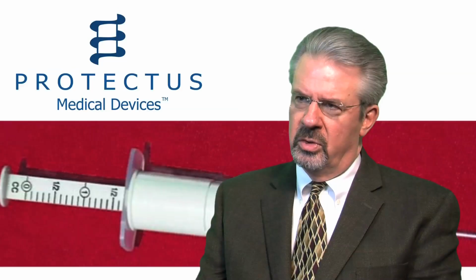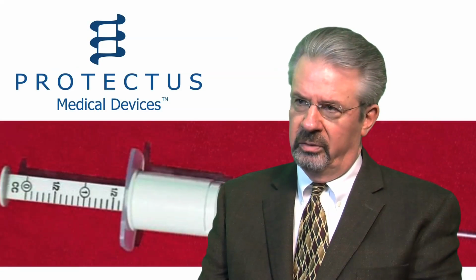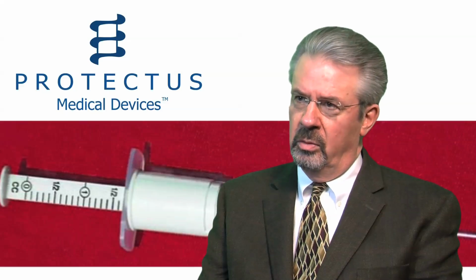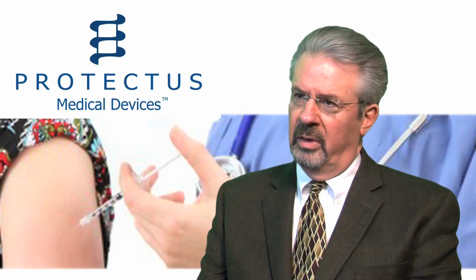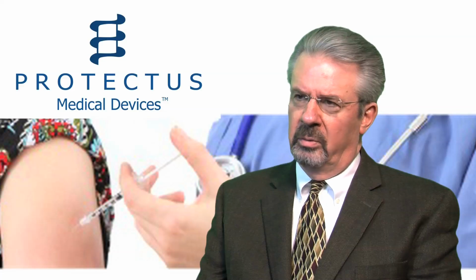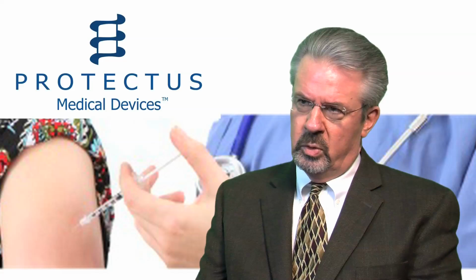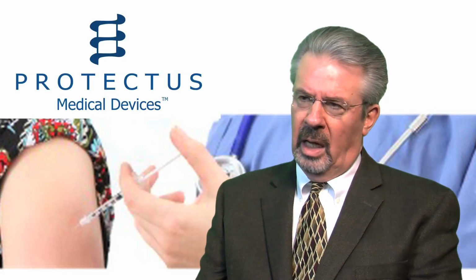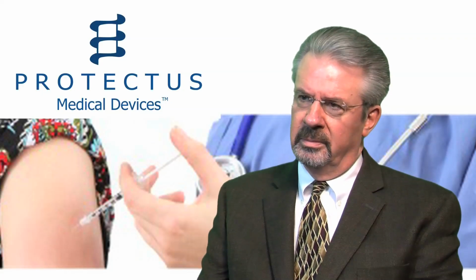The main thing that distinguishes the Protectus Medical Safety Syringe from all the competitive devices is that it is automatic and self-sheathing. That means the user does not have to do anything intentional, consciously, to deploy the safety mechanism. The syringe is priced at the low end of the spectrum of all safety syringes on the market today. The syringe was designed such that it was manufacturing friendly. Indeed, the individual parts can be put together in a very logical, logistical fashion very easily, and it keeps the cost of production down.